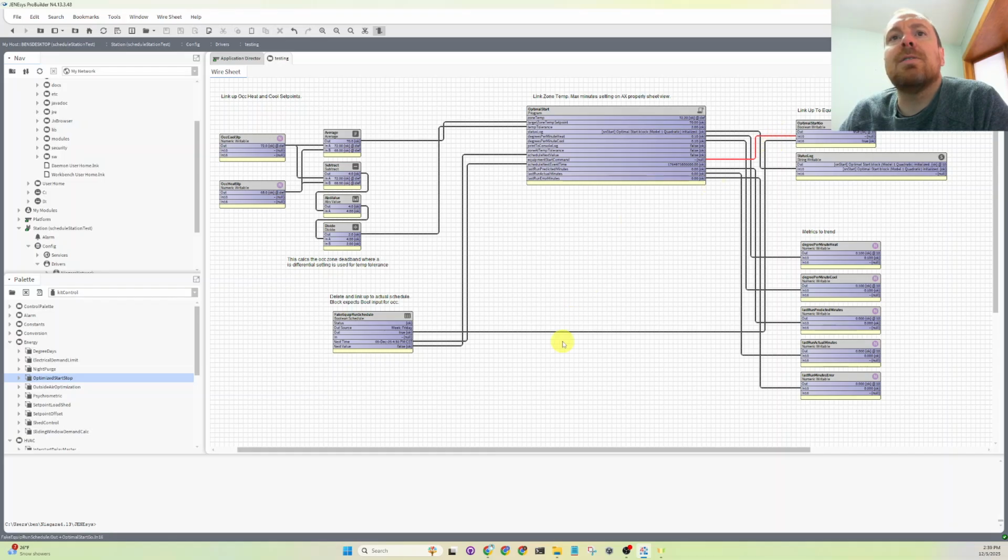So our schedule on the building automation system, we could be writing to it at priority 16, but the optimal start block writes to it at a higher priority. So if we're calculating that we need to recover the zone for a warm up or a cool down, this will go true right here, and then it'll continuously tune itself.